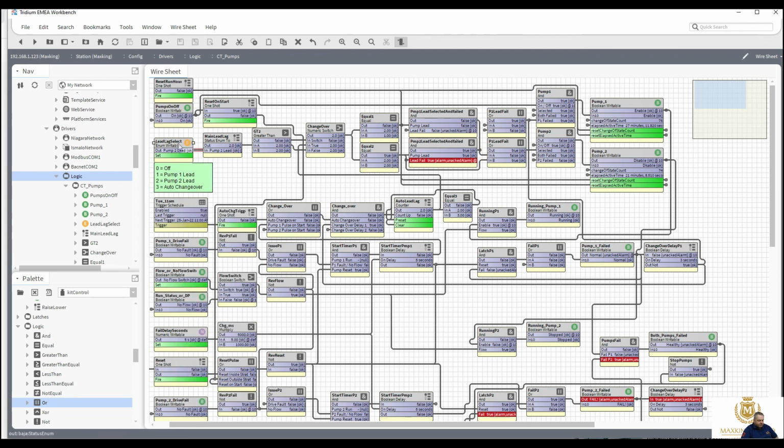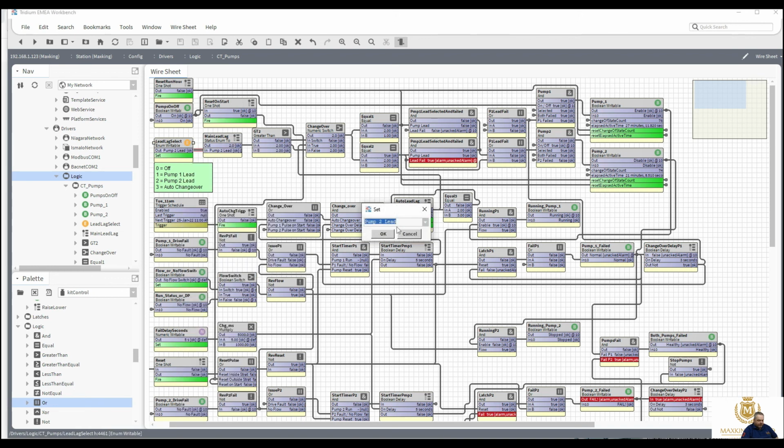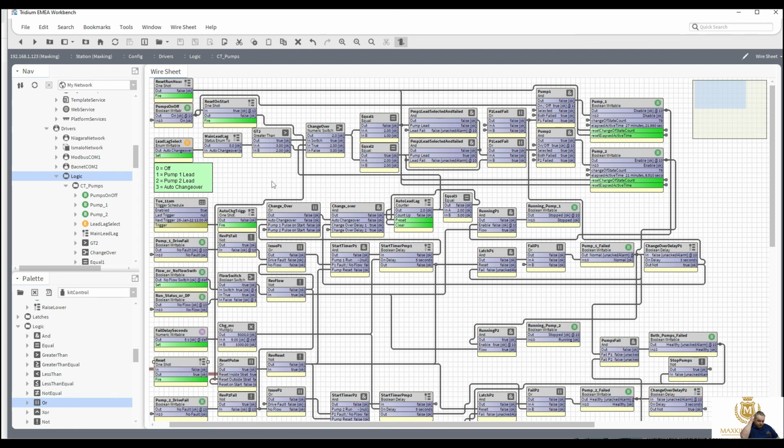Actions, emergency auto. Not emergency auto, take it off. Let me just change that now. Set auto changeover, which will be the default that's being used. Reset faults. Fire. So this AND gate will never come into play now, but the OR gate will still come into play, so these falses here will never come into play. It will always be this one now, but that works.